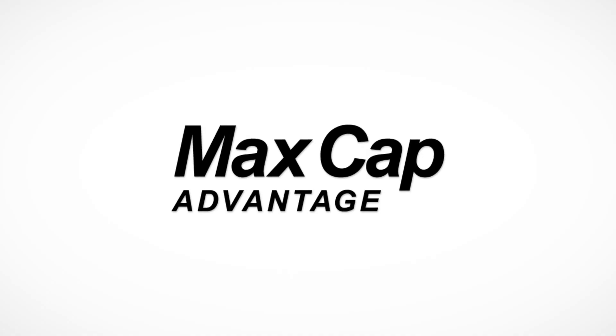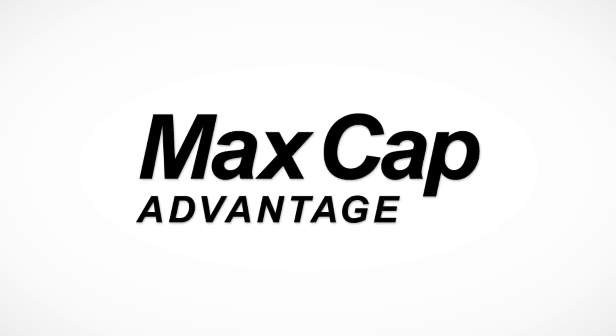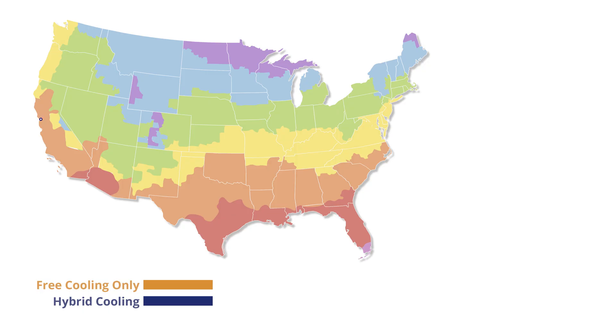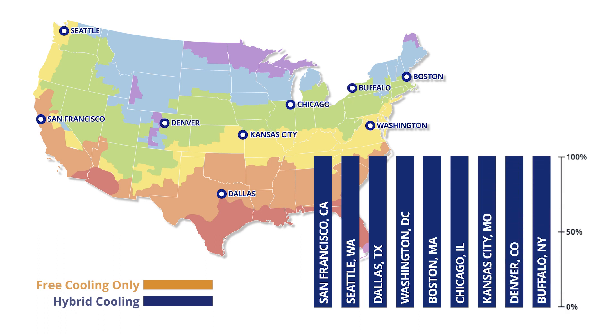The result of these operational benefits is known as max cap advantage. In short, this allows the owner to maximize free cooling benefits across all operating conditions, maximizing energy savings. It's important to note that when ambient temperatures allow a system to take advantage of free cooling, a large majority of the hours occur in hybrid mode. For example, in data center applications it can range from 70 to 100% of the operating hours. Therefore, maximizing the free cooling capacity, especially in the high-hour hybrid mode operation, will be key to optimizing your energy savings goal.